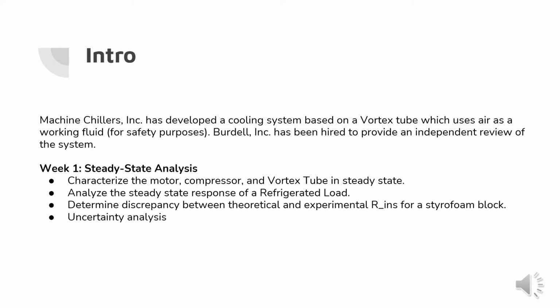Machine Chillers has developed a cooling system which is based on the vortex tube, and Burdell Inc. has hired us to provide an independent review of the system. In week 1 we looked at the steady state, where we characterized the motor, compressor, and the vortex tube, and we analyzed the steady state response of the refrigerated load. And then we determined the discrepancy between theoretical and experimental insulation resistance of a styrofoam block. And we did uncertainty analysis.